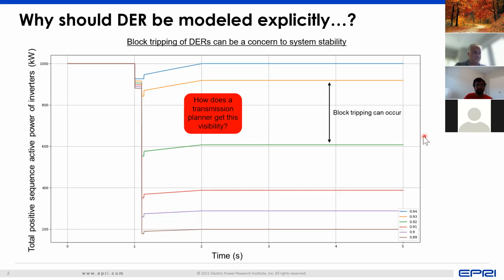Further, the tripping is in a way nonlinear. The voltage is reduced in a linear sense, where you have a 1% decrease linearly, but you can see that the tripping that occurs is nonlinear, where the spacing between these trips is not in equal increments. Having visibility of this nonlinear tripping is a challenge for transmission planners, because they can't represent the entire distribution system in detail. That would mean representing a very large system, and it would take ages to solve one simulation. So the majority of the research work that we're doing is to understand how we can get visibility of the tripping that can occur on the distribution side to enable transmission planners.